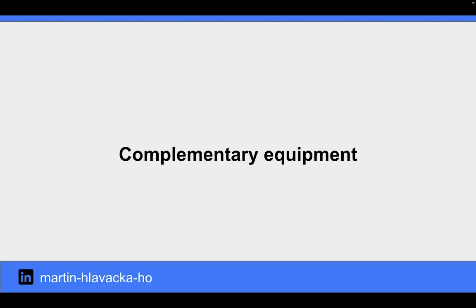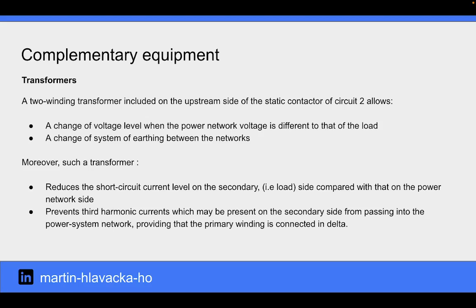Complementary equipment. A two-winding transformer included on the upstream side of the static contactor of circuit 2 allows a change of voltage level when the power network voltage is different to that of the load, and a change of the system of earthing between the networks. Moreover, such a transformer reduces the short circuit current level on the secondary side compared with that on the power network side, and prevents third harmonic currents that may be present on the secondary side from passing into the power system network, providing that the primary winding is connected in delta.